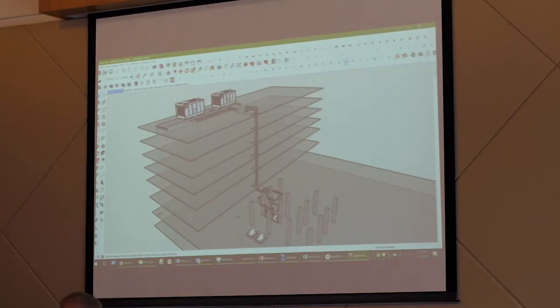This is 14-inch pipe. The flow rate, if just the modular chiller is running, is 200 gallons per minute. The flow rate in a transitional operating mode... They never run the centrifugal or the absorber together for a load. They run it to transition. The centrifugal is there for when they don't need the absorber as a heat sink for the cogen plant. So the only time they run the absorber is when they need a heat sink for the cogen plant. In other words, the refrigeration energy is free. So there's a period of time when you're transitioning where all three of those chillers are running. Flow rate then is about 3,400 gallons per minute.